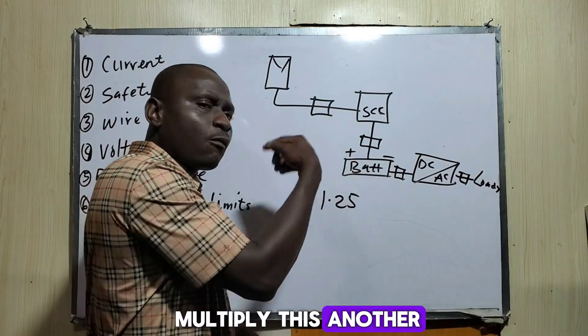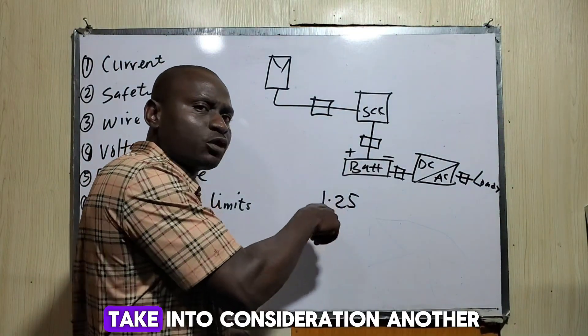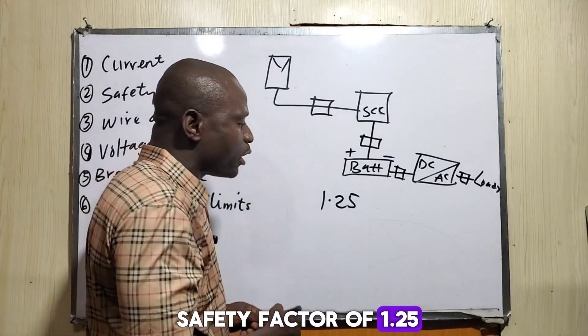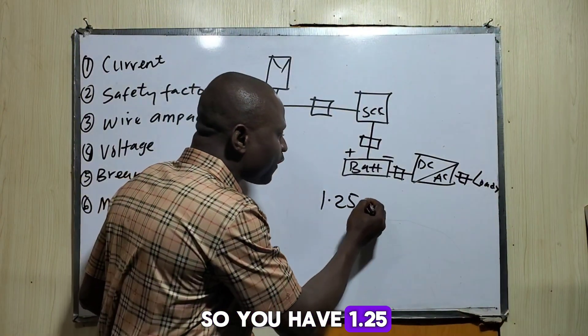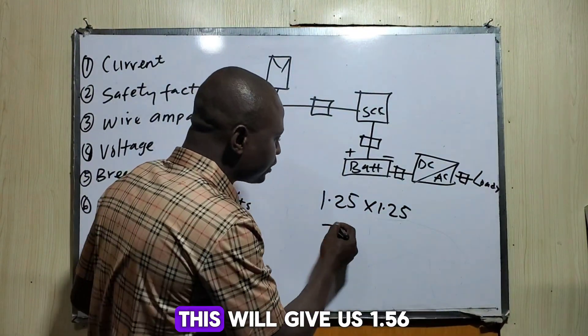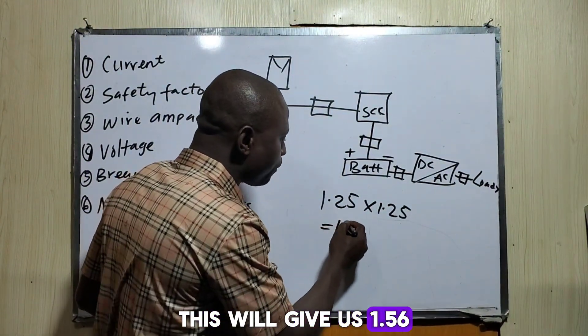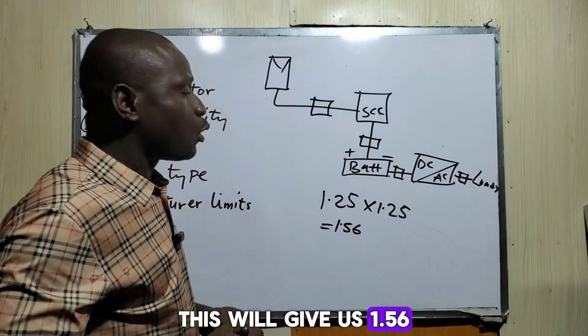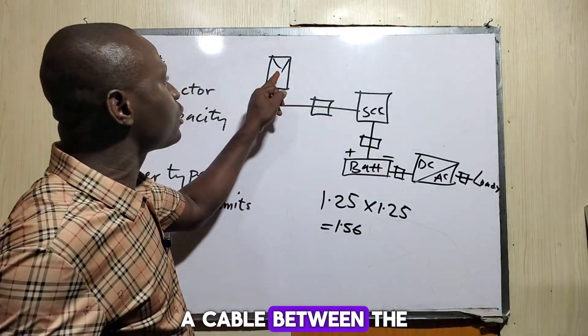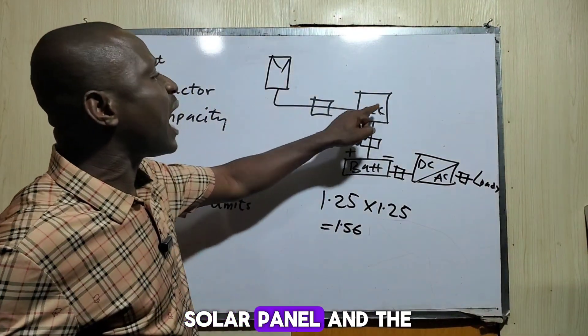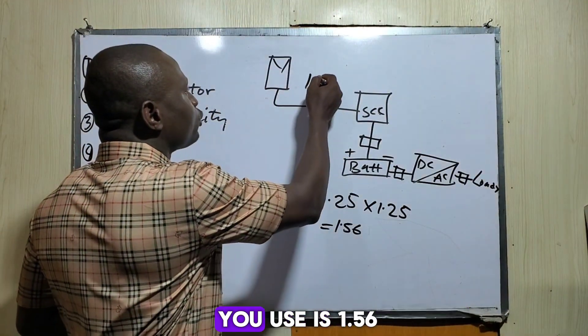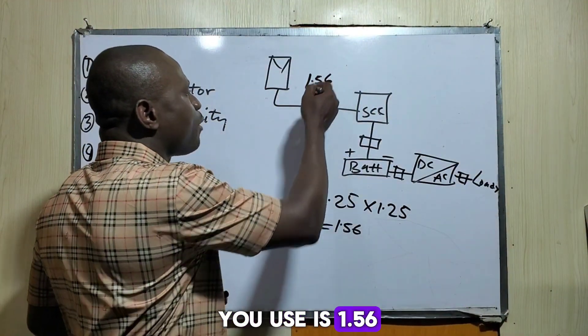You then need to multiply by another safety factor of 1.25. So you have 1.25 multiplied by another 1.25, which gives us 1.56. When sizing a breaker, fuse, or cable between the solar panel and the solar charge controller, the safety factor you use is 1.56.